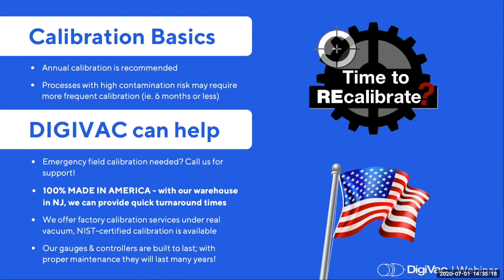accuracy specs. I can say anecdotally, after having worked here for coming up on 8 years now and performed hundreds, if not thousands, of repairs and calibrations in that time, I receive gauges regularly that are 10 or 15 years old and require very little maintenance over time, possibly a software update, a new cable, a broken sensor from time to time. But our instruments, with proper maintenance, can and do last for many years.